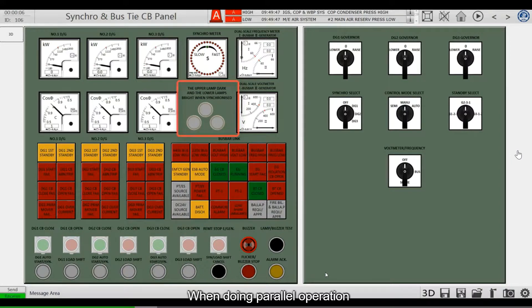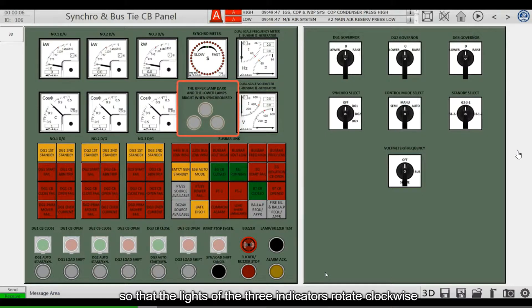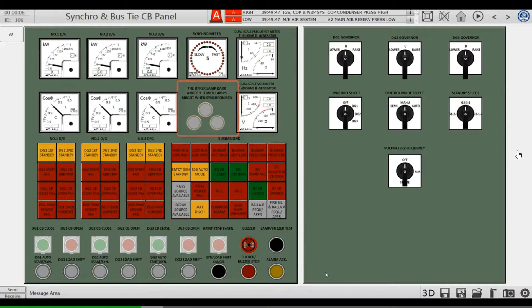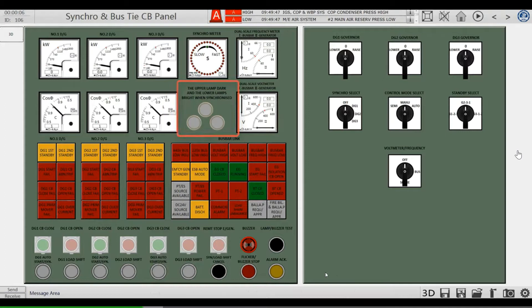When doing parallel operation, adjust the speed of the incoming generator so that the lights of the 3 indicators rotate clockwise. With the upper lamp dark and the lower lamps bright, it is the best time to close.